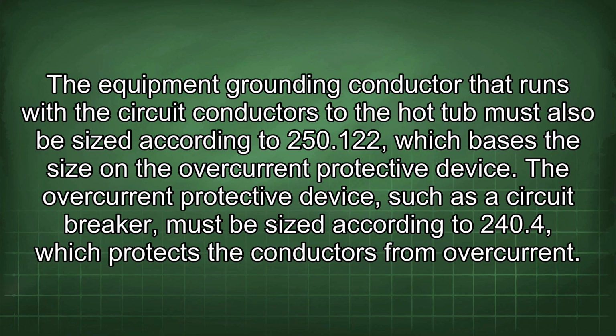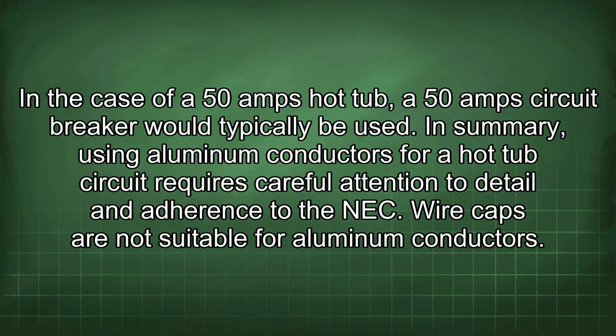The equipment grounding conductor that runs with the circuit conductors to the hot tub must also be sized according to 250.122, which bases the size on the overcurrent protective device. The overcurrent protective device, such as a circuit breaker, must be sized according to 240.4, which protects the conductors from overcurrent. In the case of a 50 amp hot tub, a 50 amp circuit breaker would typically be used. In summary, using aluminum conductors for a hot tub circuit requires careful attention to detail and adherence to the NEC.